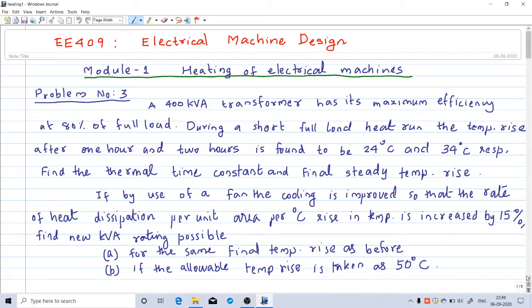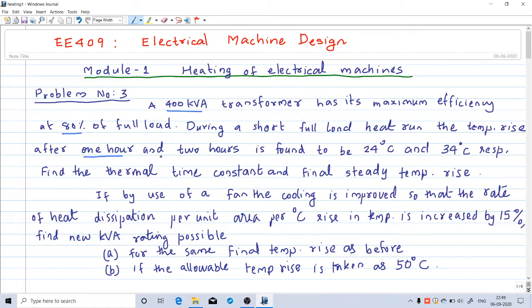Welcome to this video. We will solve a numerical problem based on heating of electrical machines. The rating of the transformer is 400 kVA and it has maximum efficiency at 80% of full load. During a heat run test, the temperature rise after 1 hour is 24 degrees Celsius and after 2 hours the temperature rises 34 degrees Celsius. It is asked to calculate the thermal time constant and the final steady temperature rise.